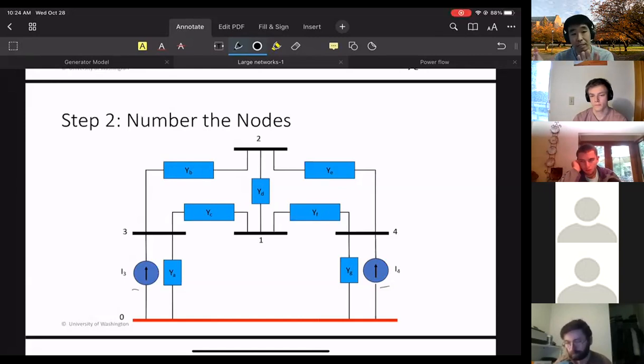When I design the grid, I imagine all the voltages are plus or minus 5% from the nominal value. I need to check this by solving this nodal analysis. Also remember, when we look at a transmission line, we said the transmission line has a stability limit. We want the angle to be less than 90 degrees for sure, or less than 45 to be safe. But we don't know the angle until we do the calculation.